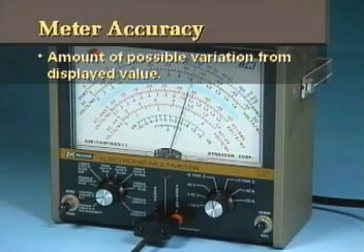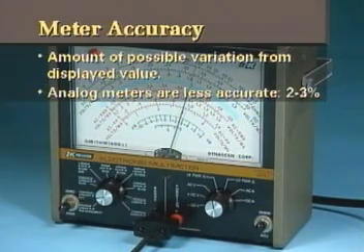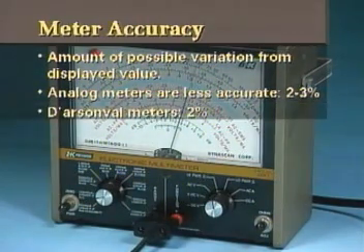As we mentioned earlier, analog meters are generally not nearly as accurate as digital meters. Normally, analog meters have accuracy ratings of 2 to 3 percent. For d'Arsonval movements, 2 percent accuracy is typical.